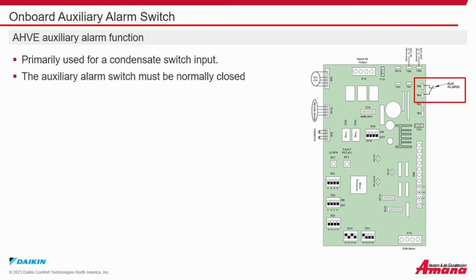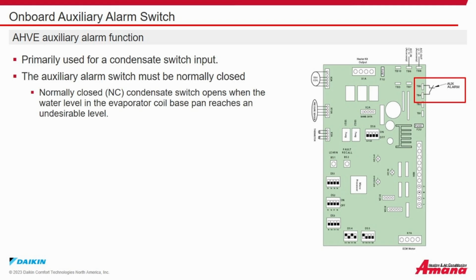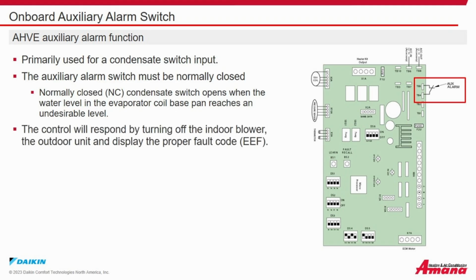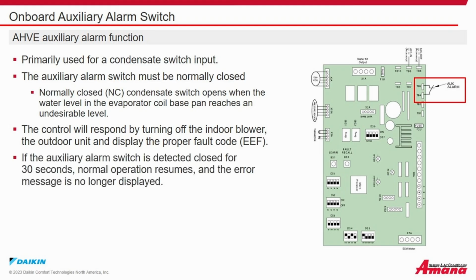The auxiliary alarm switch must be normally closed. The normally closed condensate switch opens when the water level in the evaporator coil pan reaches an undesirable level. The control will respond by turning off the indoor blower, the outdoor unit, and display the proper fault code, which is EEF. If the auxiliary alarm switch is detected closed for 30 seconds, normal operation resumes and the error code is no longer displayed.